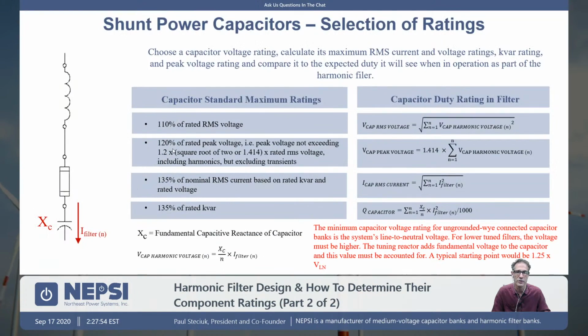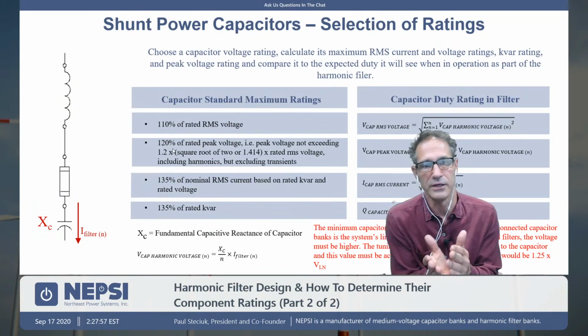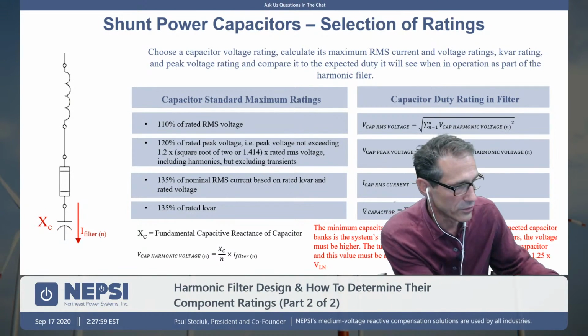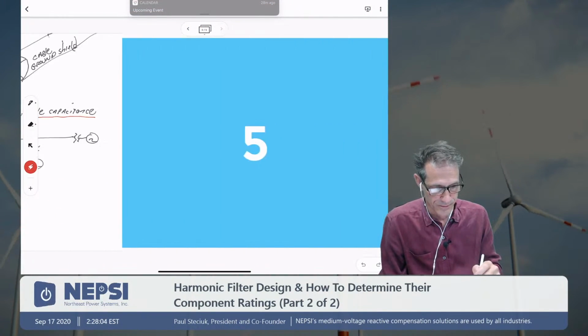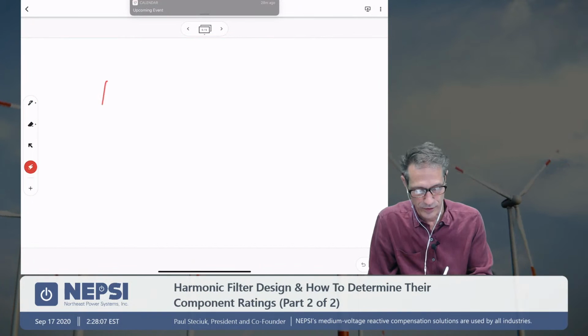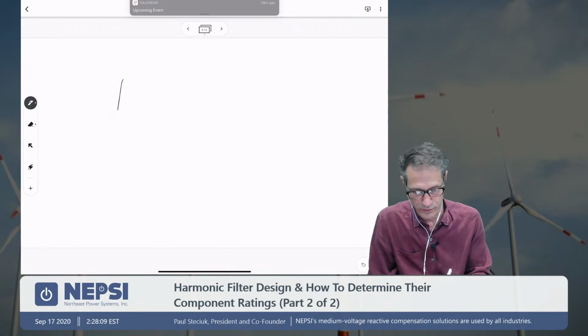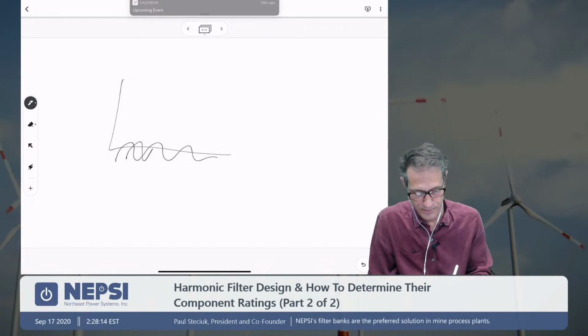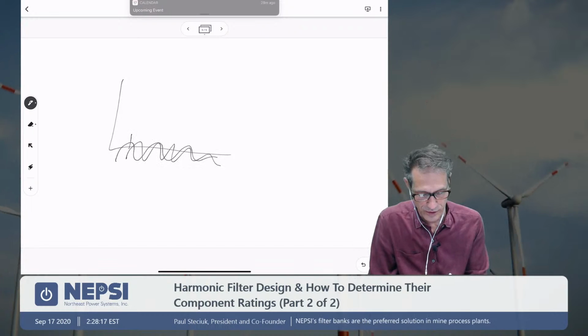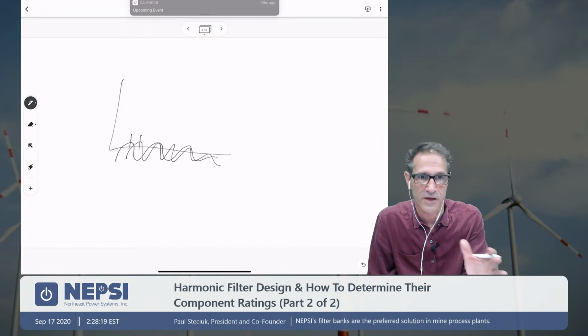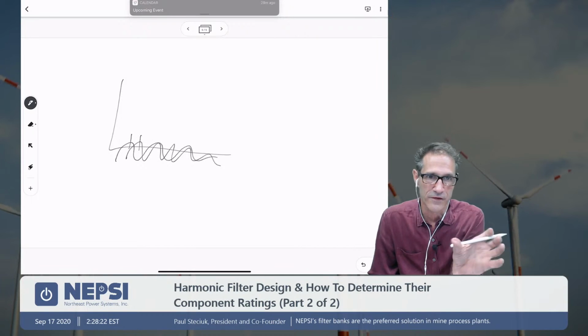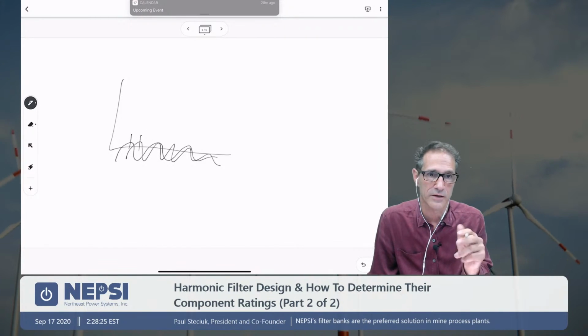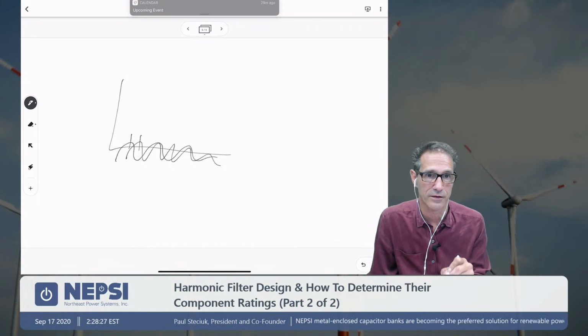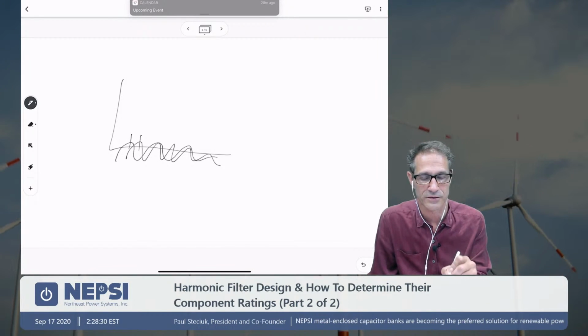You're going to check, well, if all the harmonic currents, and this is really key here, all the harmonic currents, and maybe I'll go to the iPad here real quick. Okay, so you remember you might have multiple harmonic currents, and remember that I'm not going to be very good at drawing, but remember that the peaks of these harmonic currents, the 5th and the 7th and the 11th and so on, they have different phase angles, and you want to make an assumption that all the peaks are in line with each other, and that's the worst case condition.